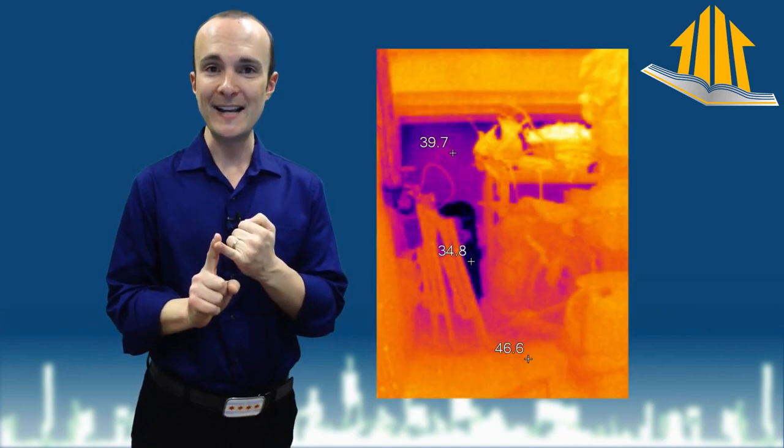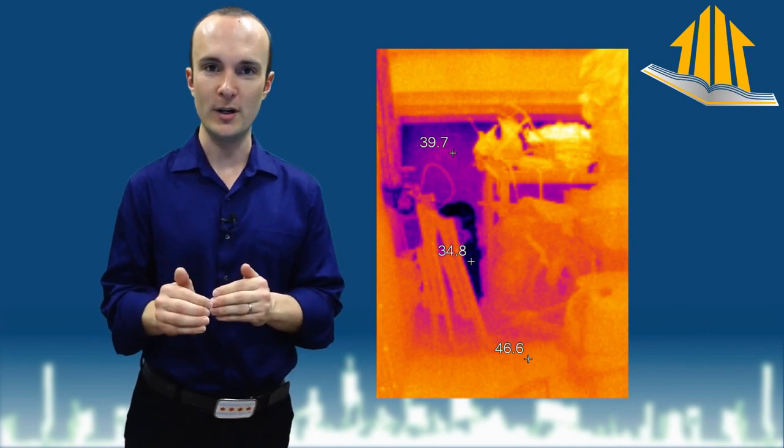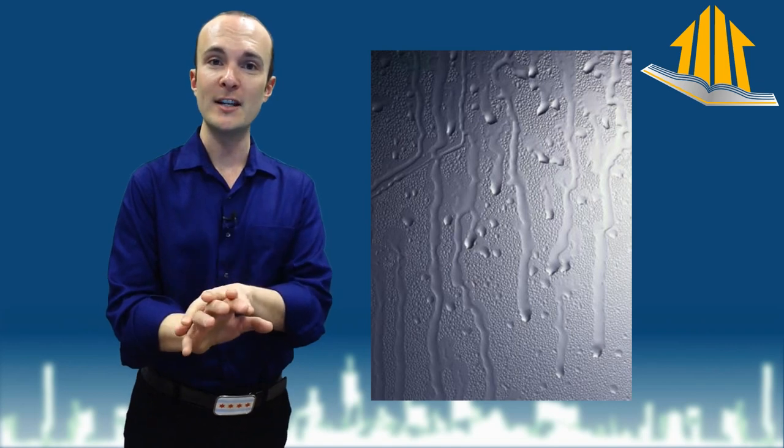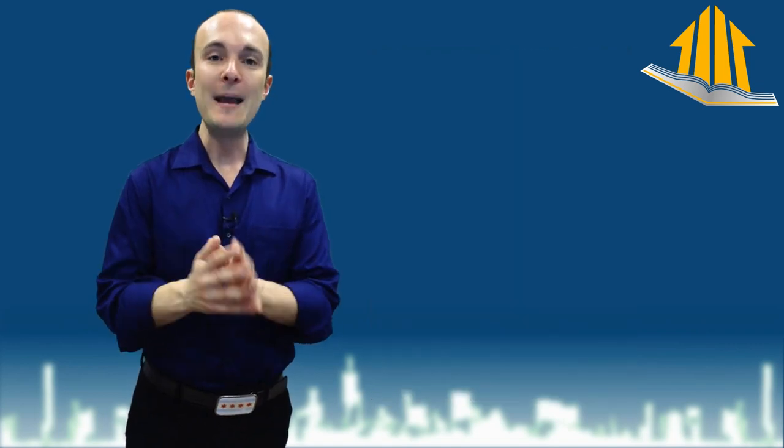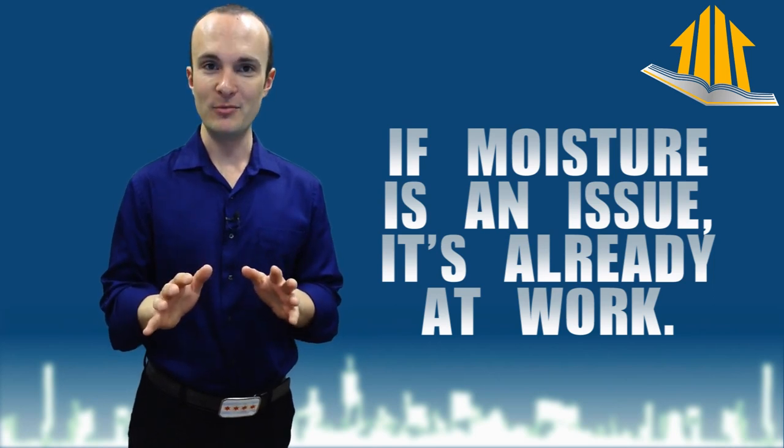Number one, when we look inside this room, everything is freezing cold in here. In fact, the way that dew point temperatures work, which means that's the temperature where a surface is going to steal the moisture out of the air and turn it into water on that surface, means that everything in this room should be soaking wet because everything is below the dew point.